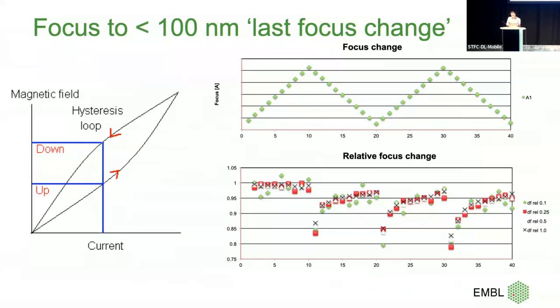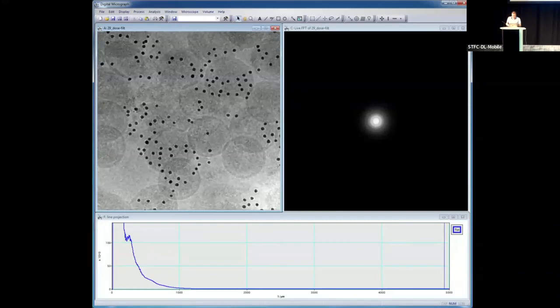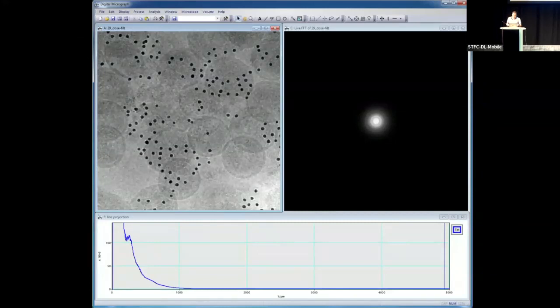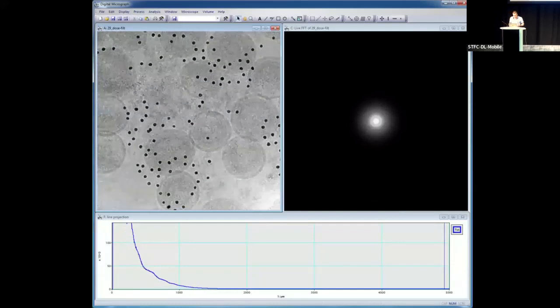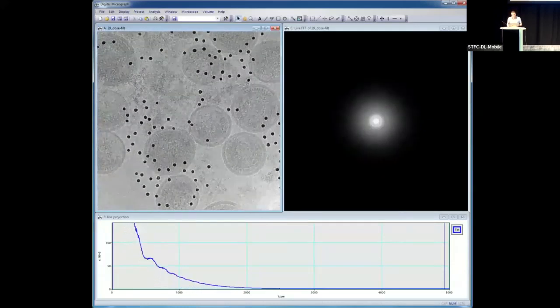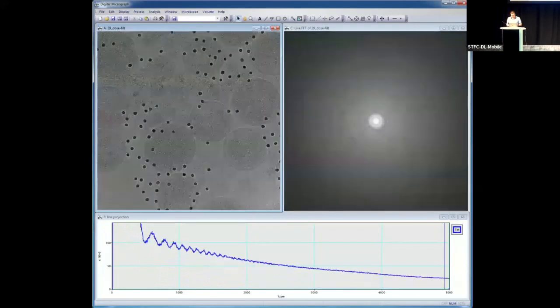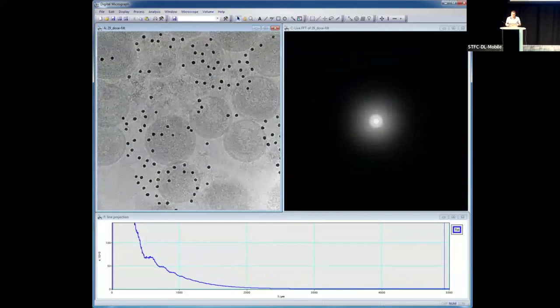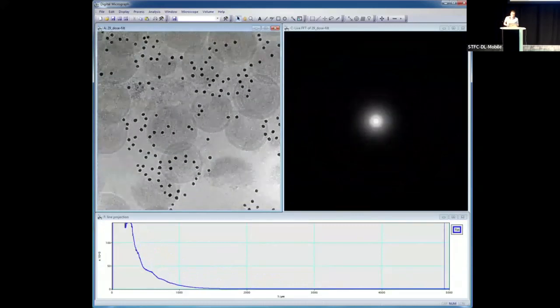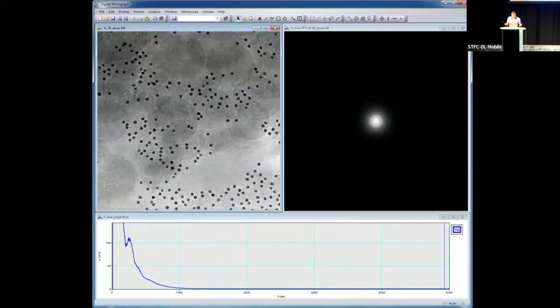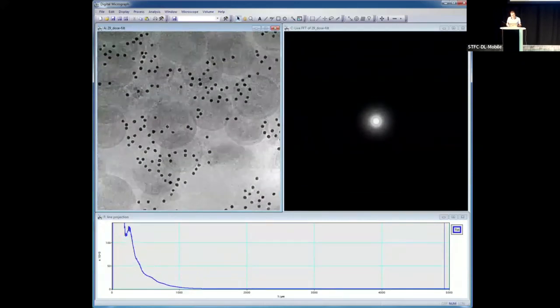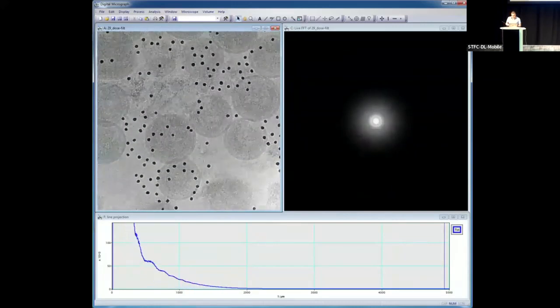I normalize the lens first, then autofocus: measure focus, apply a correction, measure again, and keep going until the last correction is less than 100 nanometers — then we know it's very accurate. At the time I thought it was a good idea, we got good data, and nobody questions you. Later I realized looking at a tomogram with dose filtering applied: at zero tilt everything looks fine, then the filtering kicks in. That makes me wonder — is accurate focusing really that important? Some people recently didn't do focusing at all, just relied on the stage and prediction, and got really good resolution.